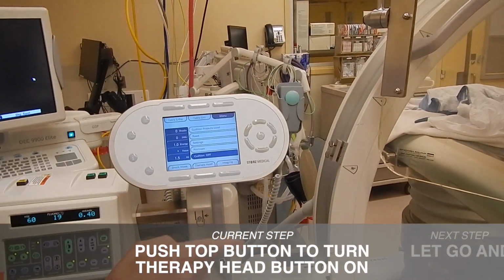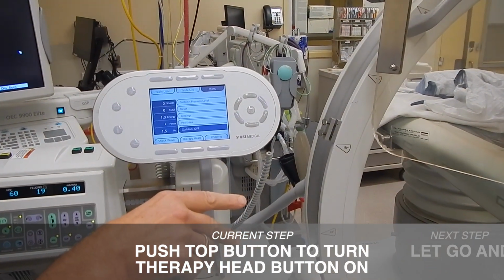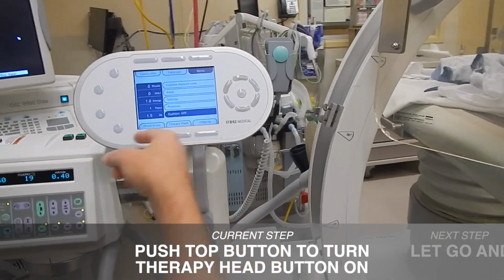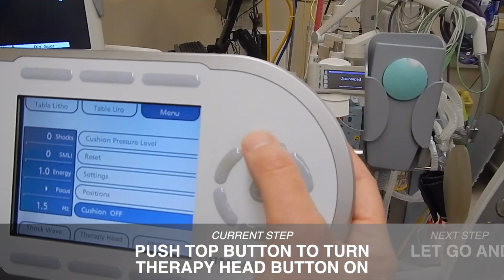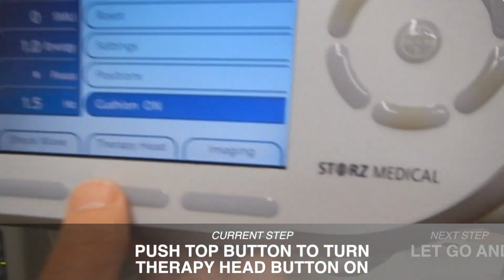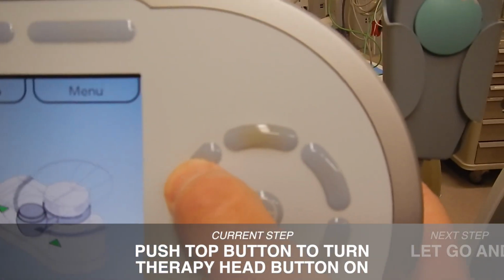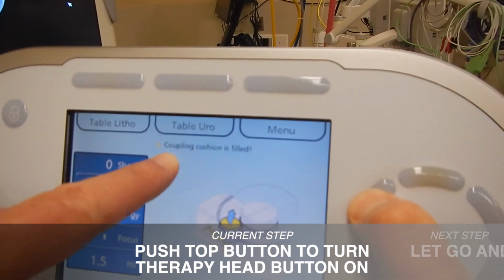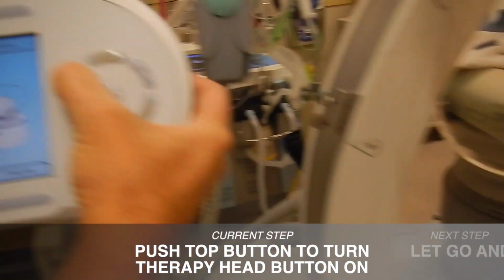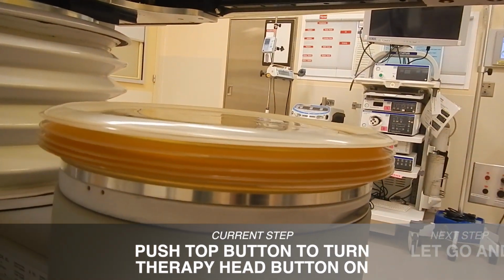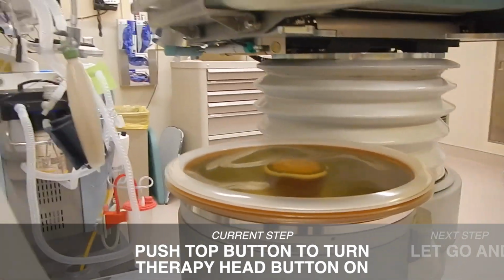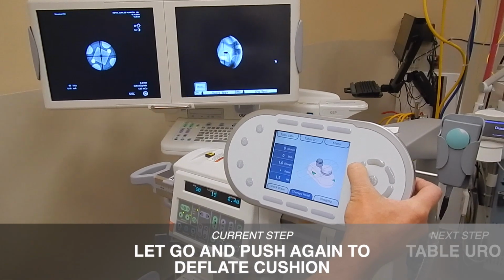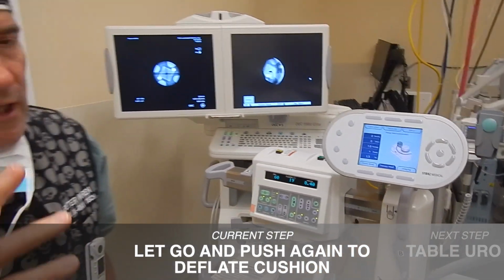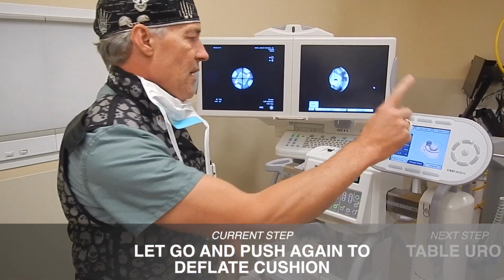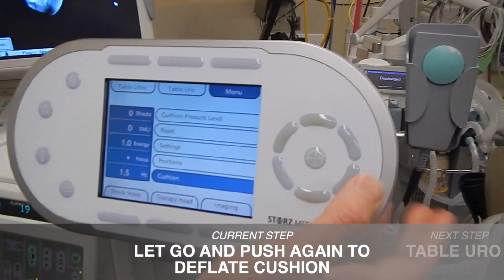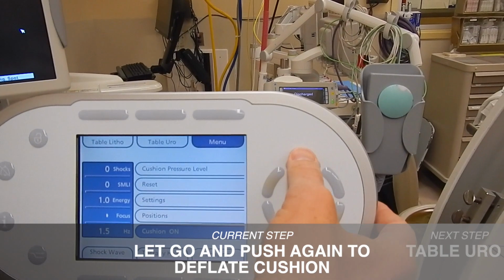I want to initiate the filling of the therapy head cushion before I put it to park position. To do that, you just press this top button, that'll turn the cushion on. Then you press therapy head mode. Then you press this, and it's telling me the cushion's filled, so let go and then press again. And if you look at the cushion, you'll see it draining. All that did was, when we're ready to bring the therapy head in for the patient shockwave, that will automatically fill up. If you forget that step, it's no big deal. You just go into menu, down to cushion, 4 o'clock, and then 12 o'clock to turn it on.